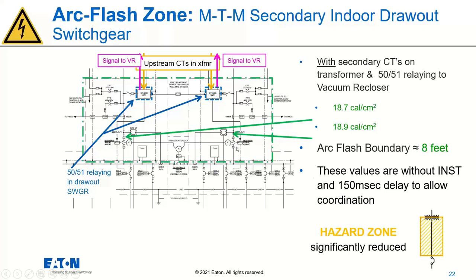And this is also not sacrificing coordination. That's another really big piece: obviously we want our feeder breakers to go off before our main breakers, and our main to go off before our vacuum recloser. So we're coordinating those all together and trying to make them trip in that certain cadence. We're able to do that without sacrificing our main breaker coordination, and we're still able to get down to that much lower energy than we were before, 8.5 times lower than that 160 calorie limit with this 50/51 relay.